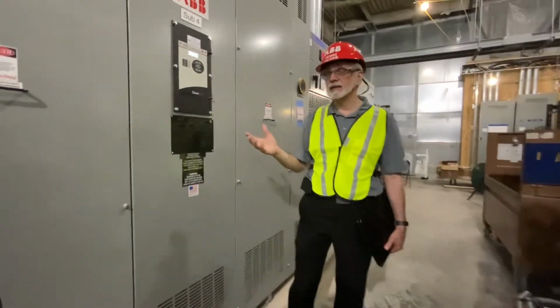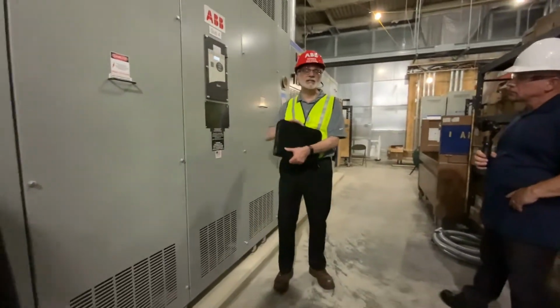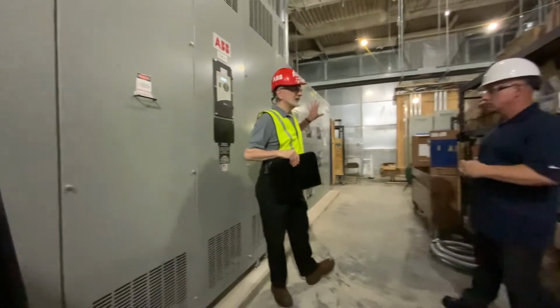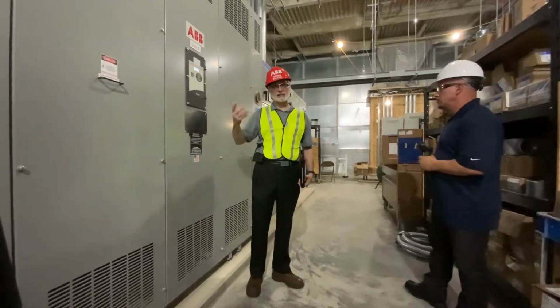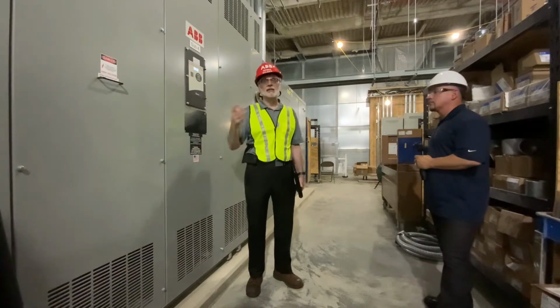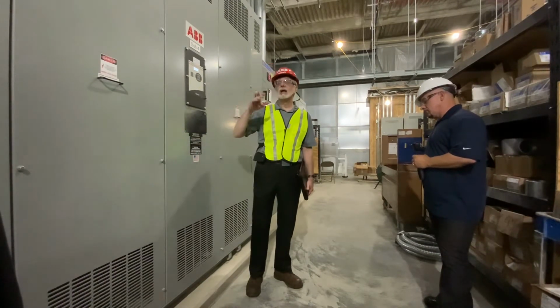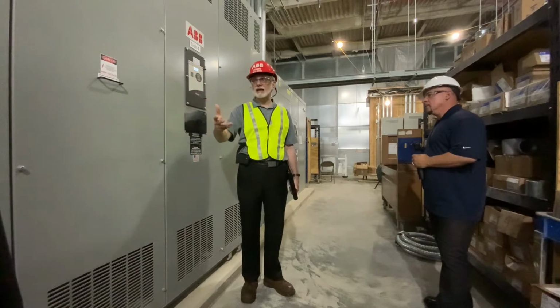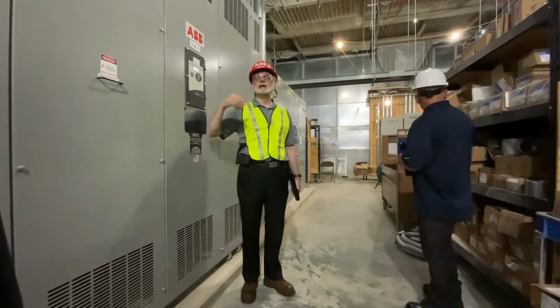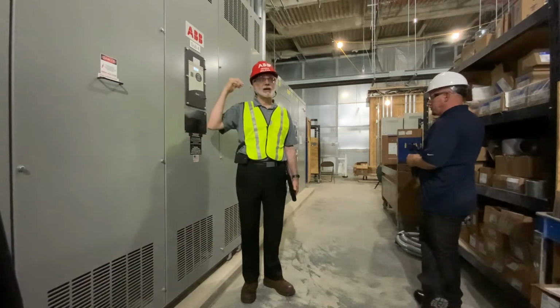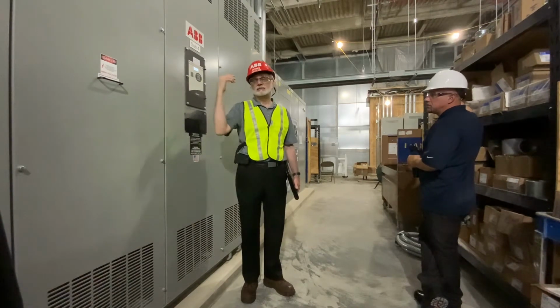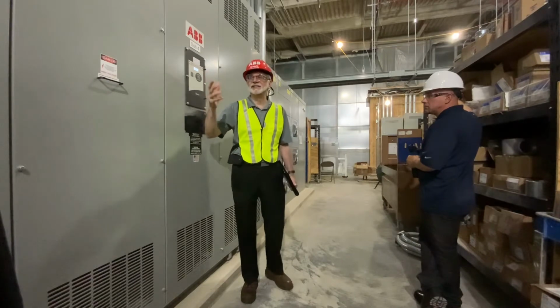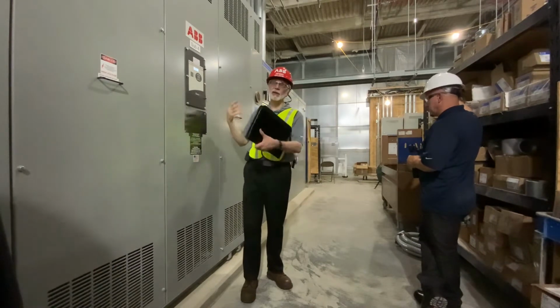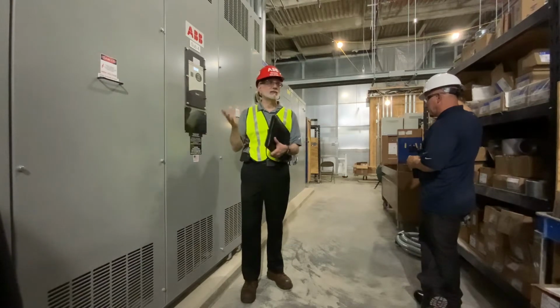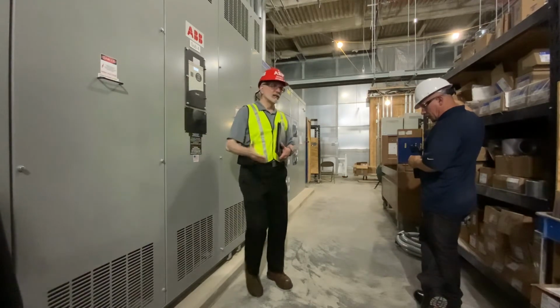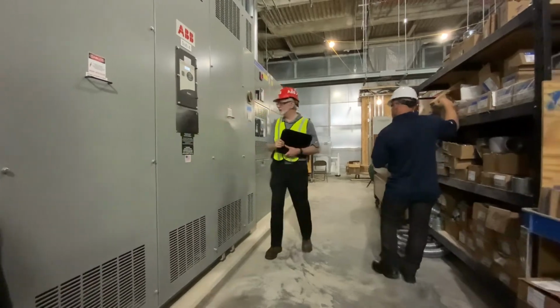So you've got some good overcapacity built in here, and the main circuit breaker is designed to accept a higher amperage than it would normally go. So the nice thing is, on that 7th day, when it's 100 degrees and everybody's running their air conditioner, even though you've asked them not to and they say, I don't care, you have a piece of equipment that's going to be able to absorb that overcapacity. I just wanted to make you aware of that. Okay, so let's move down to after it stepped down to 480.